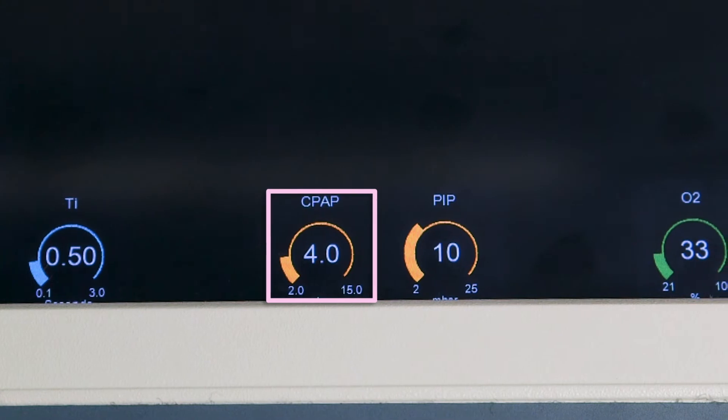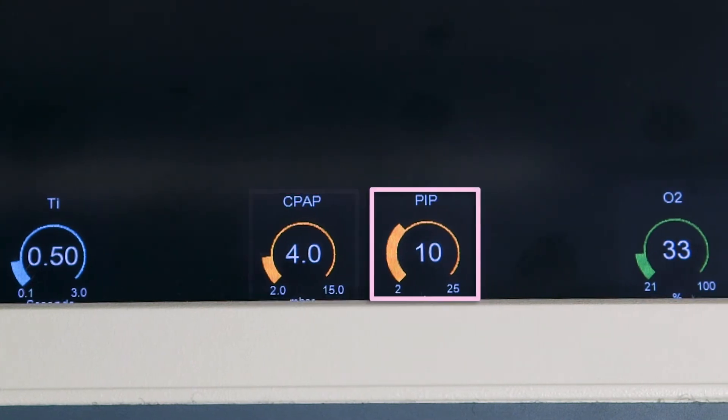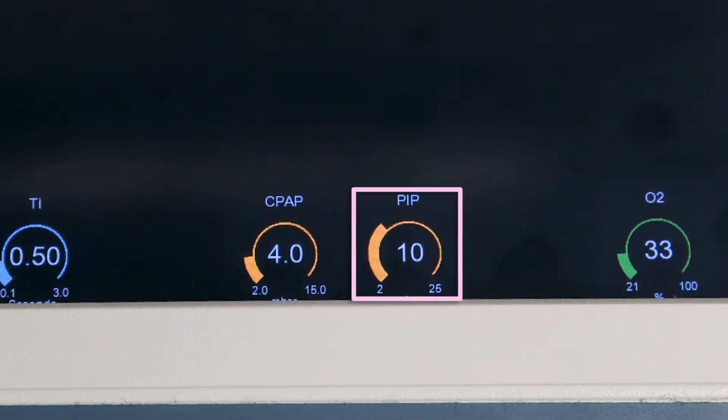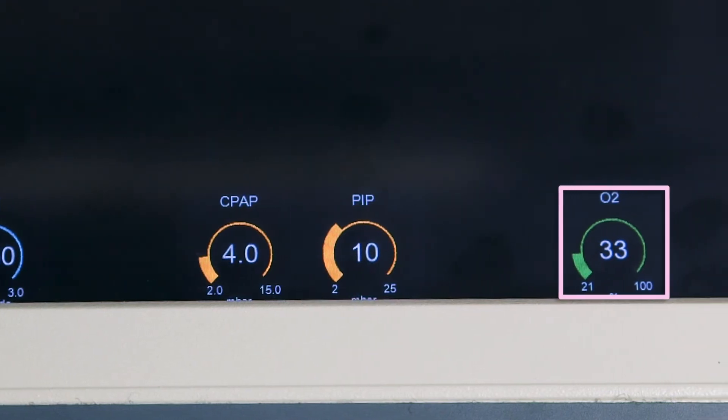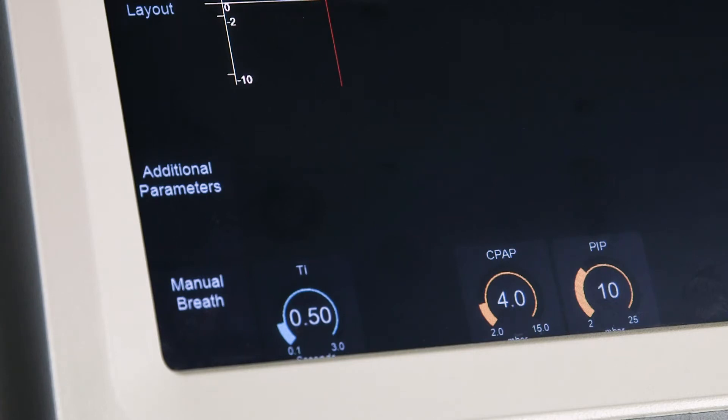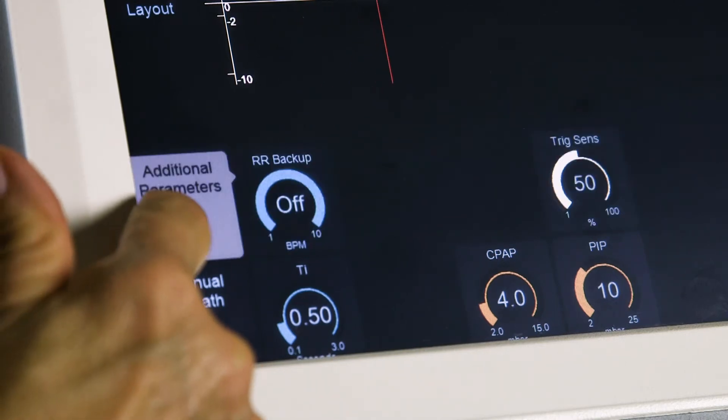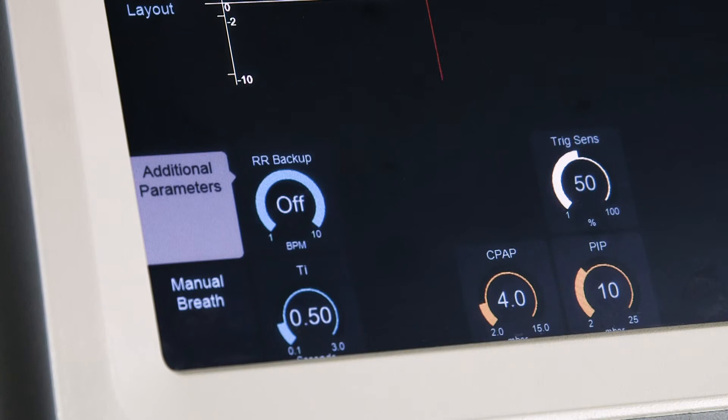CPAP, PIP, and O2 percentage to be delivered. The user can also set additional parameters, which are displayed when mode is first selected.